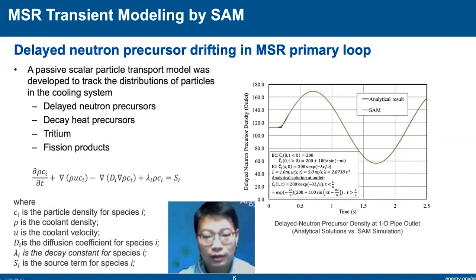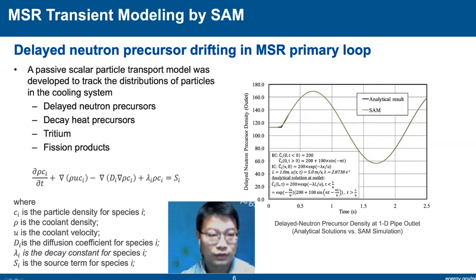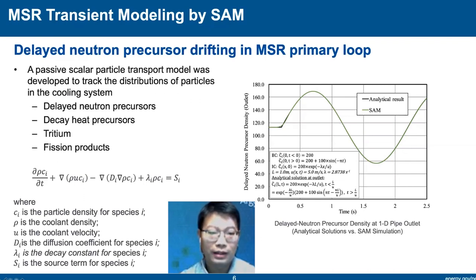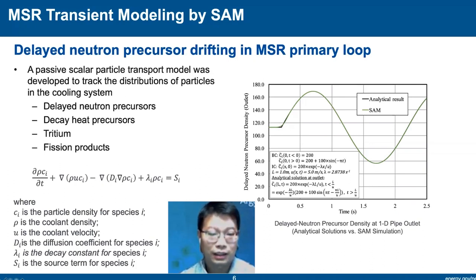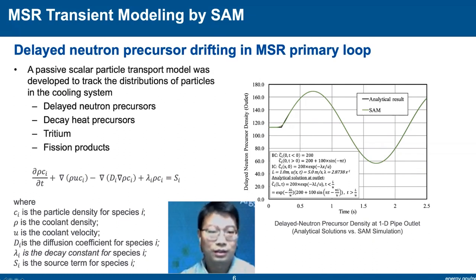For MSR transient modeling, an important feature is the delayed neutron precursor drift. We developed a general scalar transport capability so the code can capture delayed neutron precursor concentrations throughout the system. This same capability can be applied for the transport of other radioactive isotopes such as decay heat precursors, tritium, or other fission products. This forms one of the foundations for MSR transient simulation as well as mass transport inside the fluid.